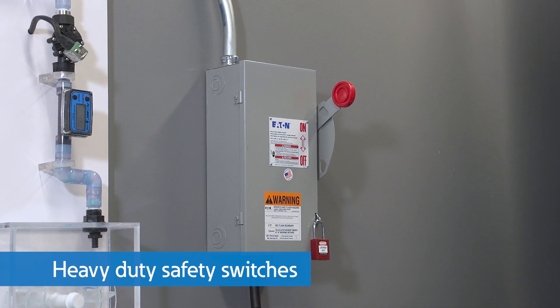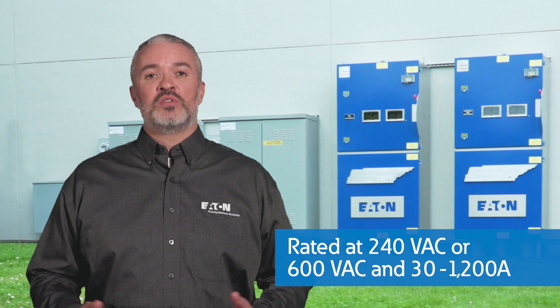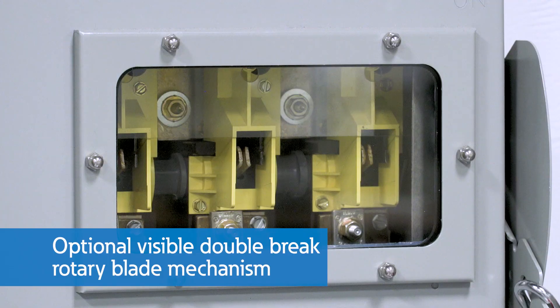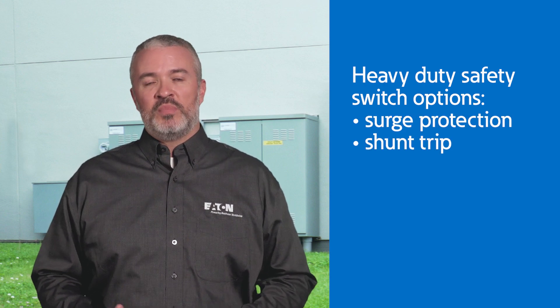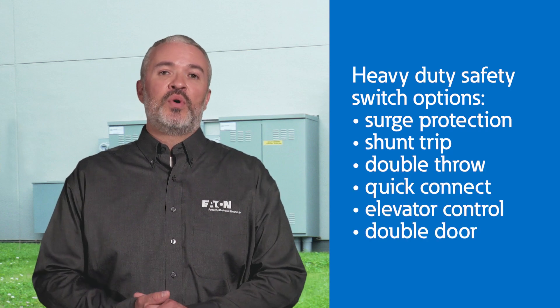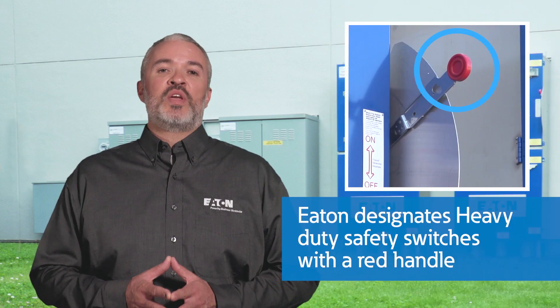Heavy duty safety switches are used in commercial, institutional, and industrial applications where reliable performance and service continuity are critical. These switches are most often rated at 240 volts or 600 volts AC and 30 to 1200 amps, with a visible double break rotary blade mechanism and are load break rated. There are many different configurations of heavy duty safety switches that include options such as surge protection, shunt trip, double throw, quick connect, elevator control, double door, and line isolation. Eaton designates these heavy duty switches with a red handle.